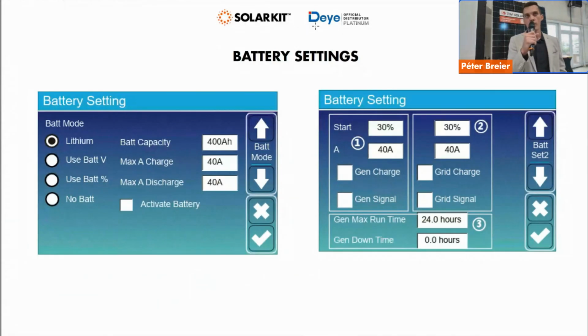So which one is the smaller should be the value here. For example, if you are using Pro B batteries, then the nominal current of the Pro B battery is 50 amps. So if you're using 3 pieces of Pro B, you should set 150 here, both on charge and on discharge. So basically, in case of lithium batteries, it's almost every time quite the same value.